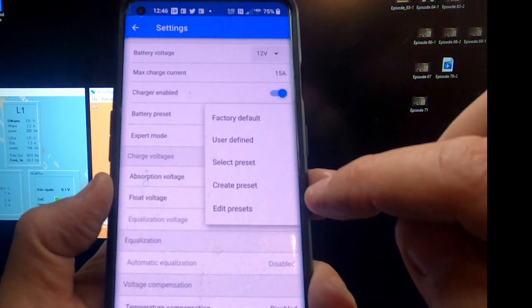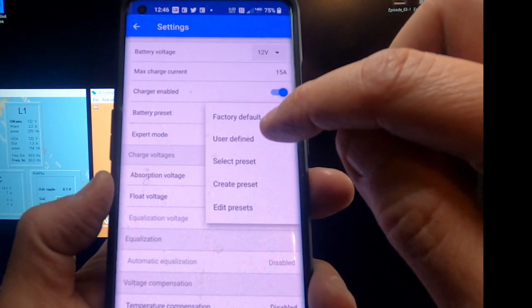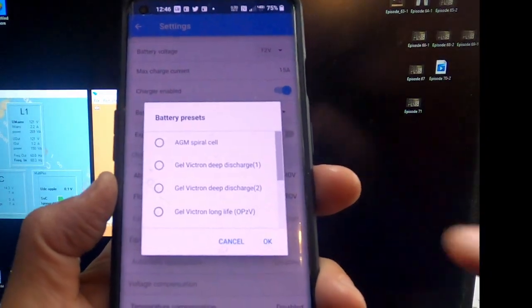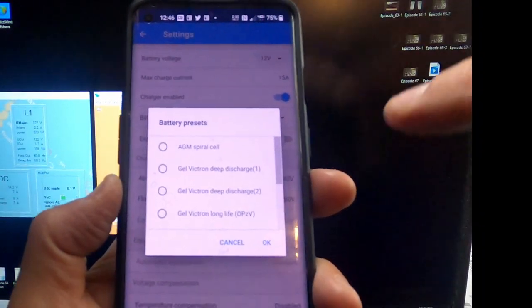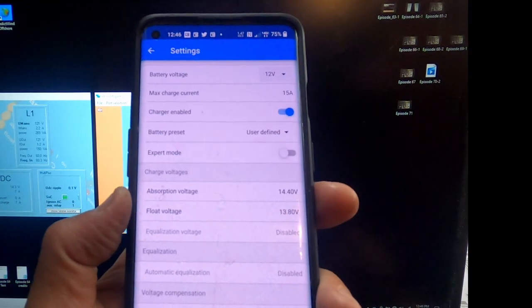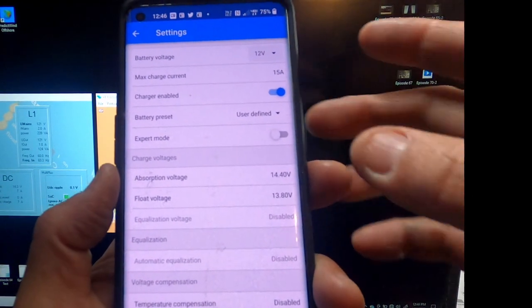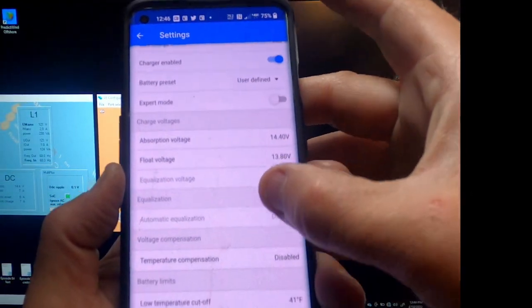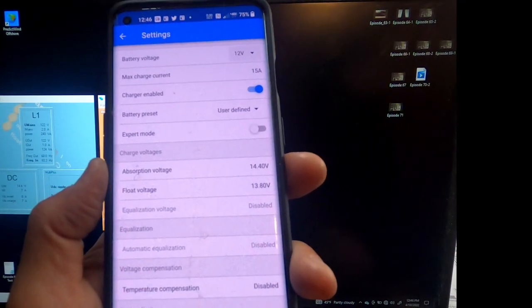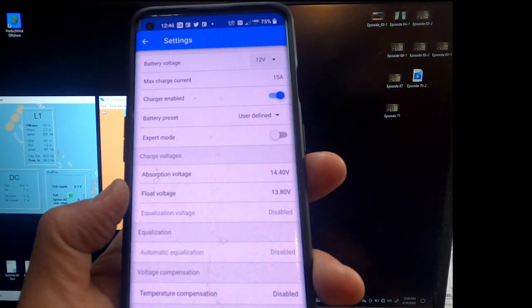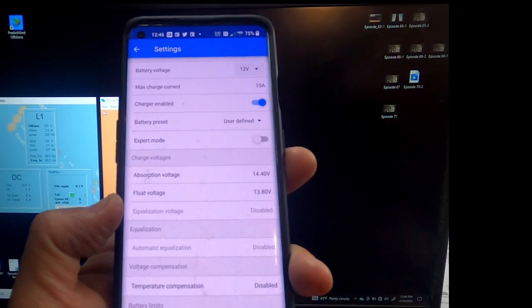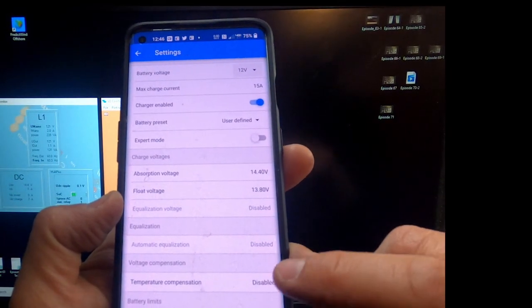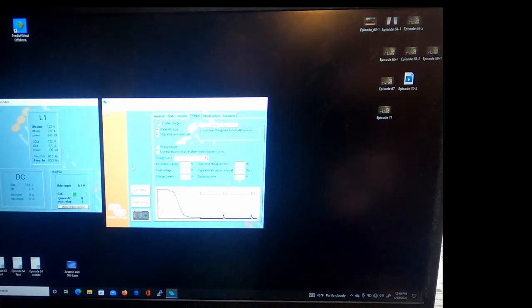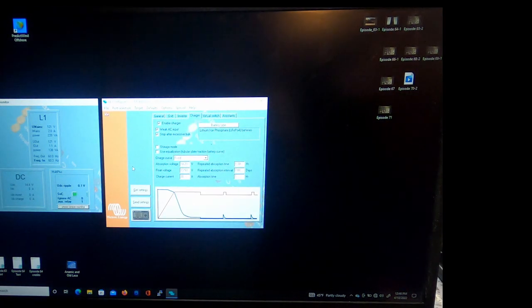There are just settings here. The predefines include lithium ion phosphate. I'm not choosing that because I'm actually specifying values that are pertinent to this particular battery. So right now our absorption voltage is set for 14.4 and 13.8 for the float voltage as required by Amperetime. And that is it, we are now configured.